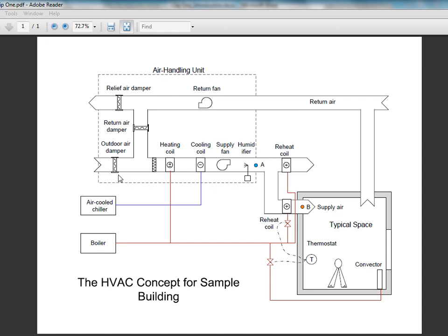The unit shall include mixing outdoor and return air dampers to provide the building with fresh air, a heating coil, a cooling coil, and an electric humidifier to maintain the conditions of supply air flow at point A — with temperature and humidity preset sufficiently low to assimilate the heat and moisture from the building throughout the year. To provide individual space temperature control, terminal hot water reheat coils located on duct runoffs to each space shall increase the supply air temperature during part-space cooling load conditions.